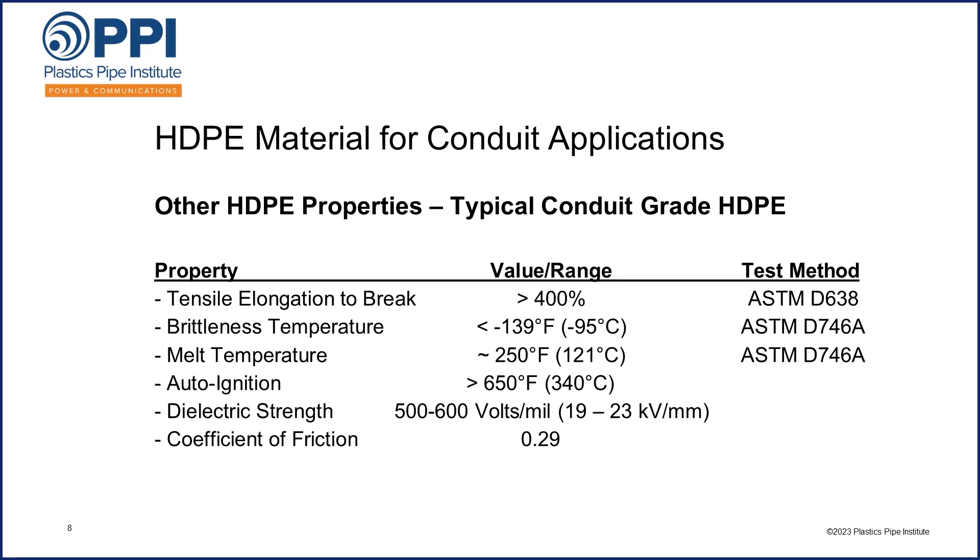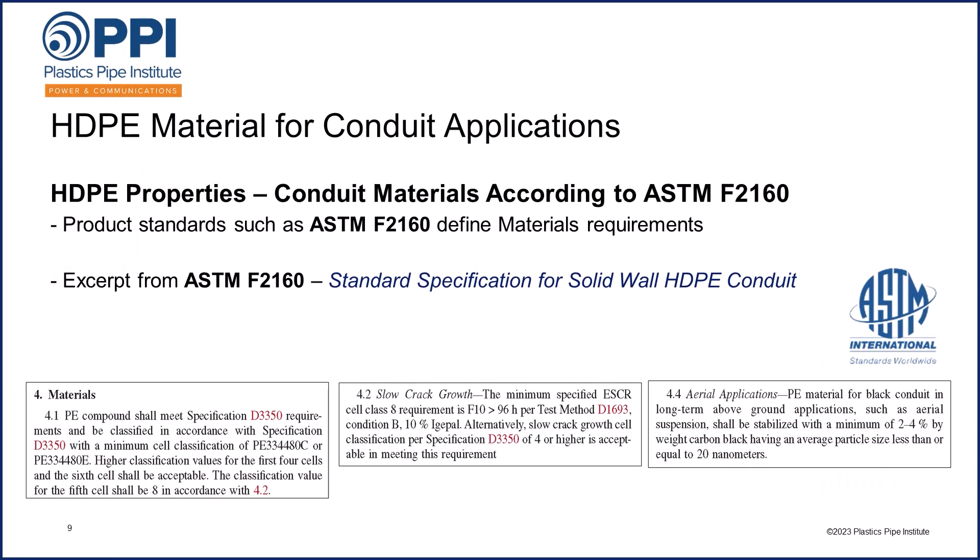Now a lot of these properties are specified in product standards. The primary product standard for HDPE conduit materials is ASTM F2160, the standard specification for solid wall HDPE conduit. Below are a few screenshots from ASTM F2160, the material section which defines exactly where those cell classification values are published and applied. In section 4.1, it is defined exactly what the minimum cell class shall be. The slow crack growth resistance is also defined in section 4.2. And for aerial applications of conduit, in section 4.4, it's defined how those products are UV stabilized against sun damage using carbon black, as those would be non-buried but exposed outdoor applications on poles.